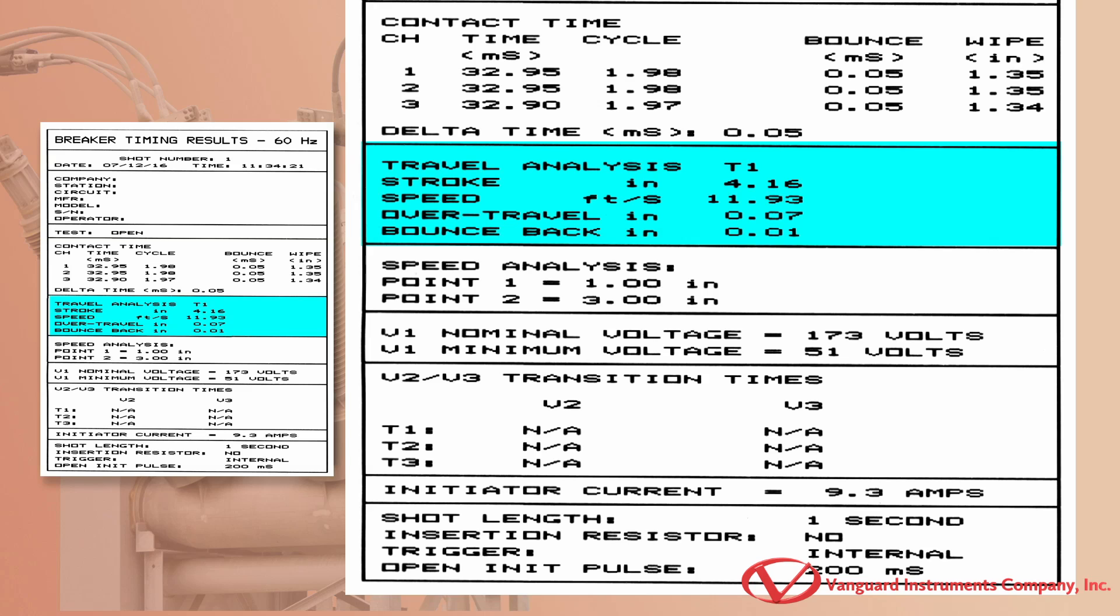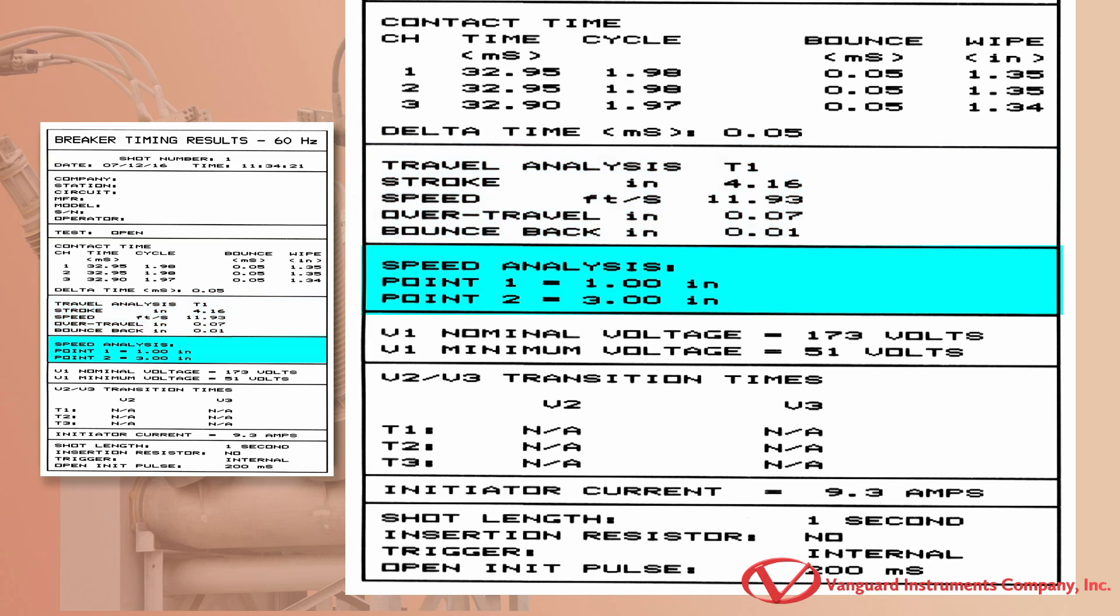The travel analysis for transducer 1 is shown here. The analysis comprises the breaker stroke, contact velocity, contact over travel, and contact bounce back. They can be displayed in either English or metric units. In order for the CT7000-S3 to calculate the contact velocity through the arc zone, the user must first define the two points on the travel curve. The two analysis points to be used are defined as AP1 and AP2.